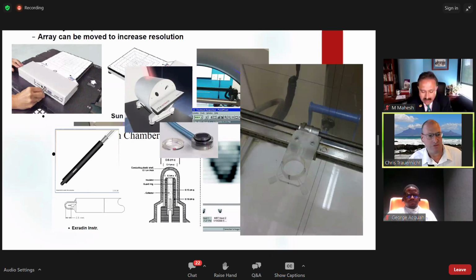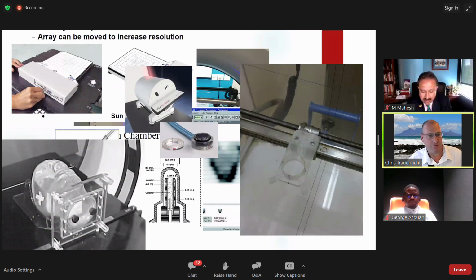This is a good time to look at phantoms. The end-to-end phantom, I would highly recommend it. You can very strongly motivate for why you need this. An electron density phantom, for example. If you don't ask for it, it doesn't automatically come with the LINAC. If you have one, great, but at least think about it.